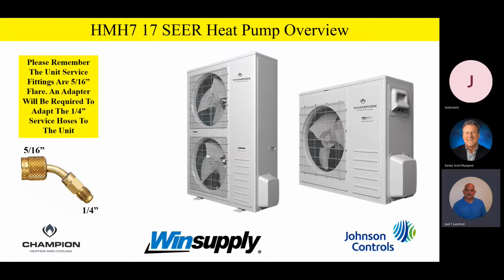You'll find these a lot of times on mini splits. And even though these are not mini split products, they still have that same type of fitting. And so these adapters, they're available from several sources, Robinair and Yellow Jacket and so forth. They all make them. But again, it's a 5/16 female to a 1/4-inch male flare fitting adapter, so they can hook their service hoses up to the unit.